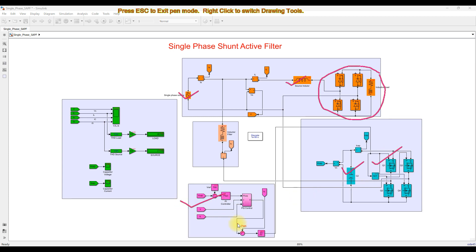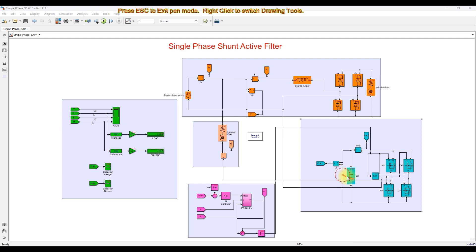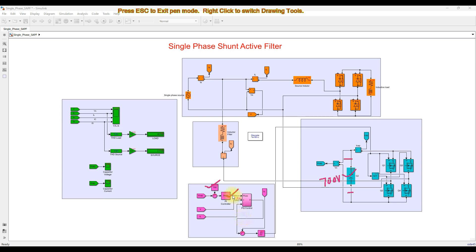Here we are using the PQ control concept. In the PQ control concept, we measure the capacitor voltage and compare it with a reference voltage. We are going to maintain the voltage across the capacitor at 700 volts. After comparing the reference with the actual capacitor voltage, it is processed via a PI controller, which generates the loss power component.